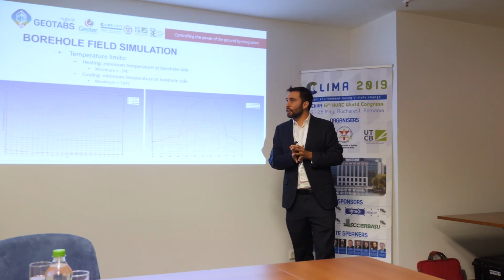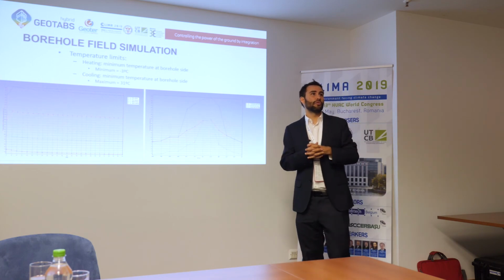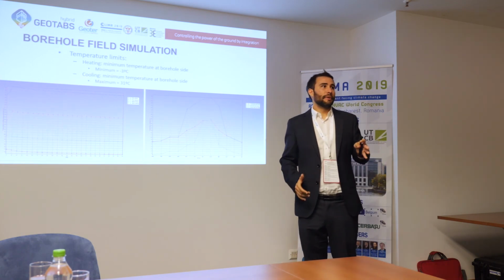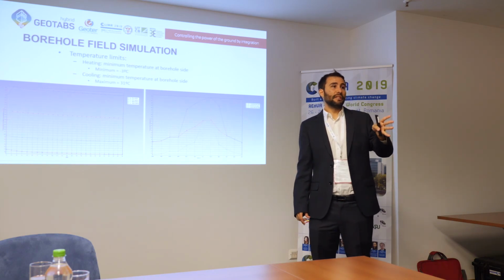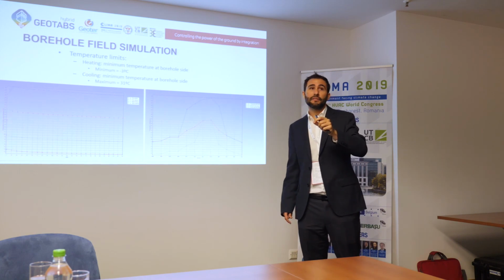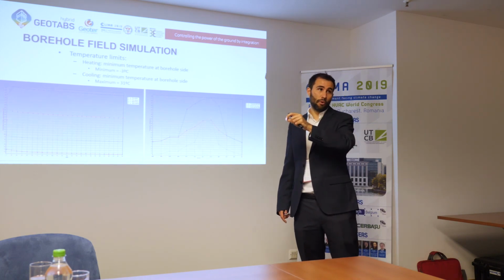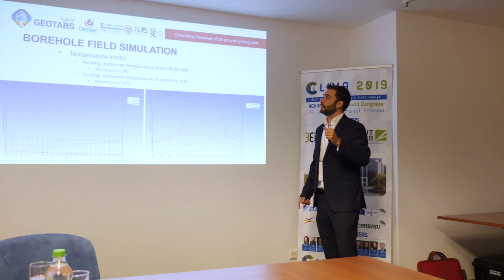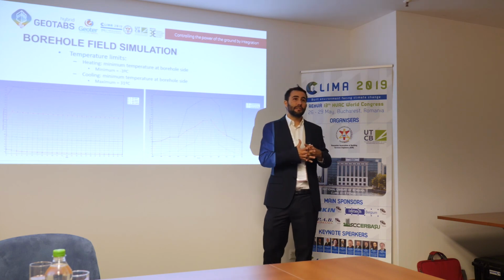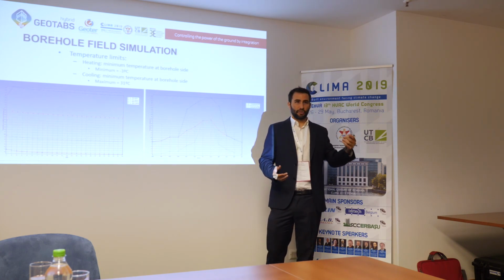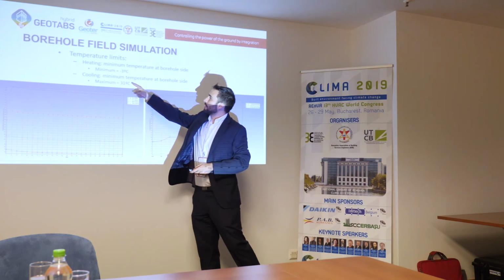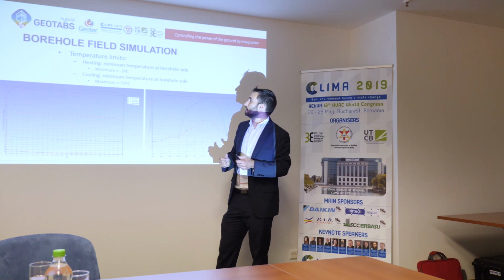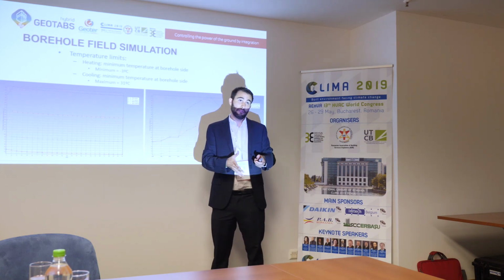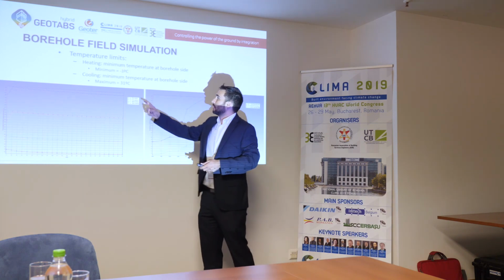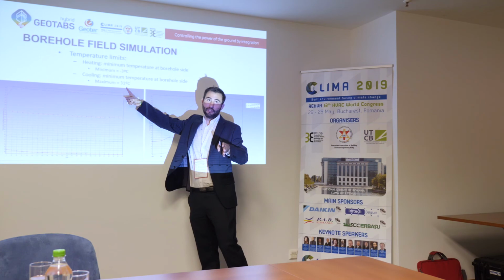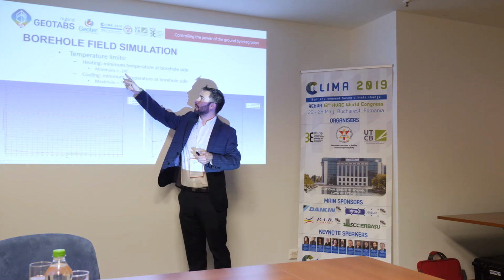Finally, I have to establish the temperature limits of my borehole site. Usually, temperature limits are plus minus 17 degrees, taking as reference the undisturbed temperature of the borehole. For example, if the undisturbed temperature of my borehole is 14 degrees, the maximum temperature of the heat fluid that I have to introduce in the software has to be 14 plus 17 degrees, 31. And the same for heating.